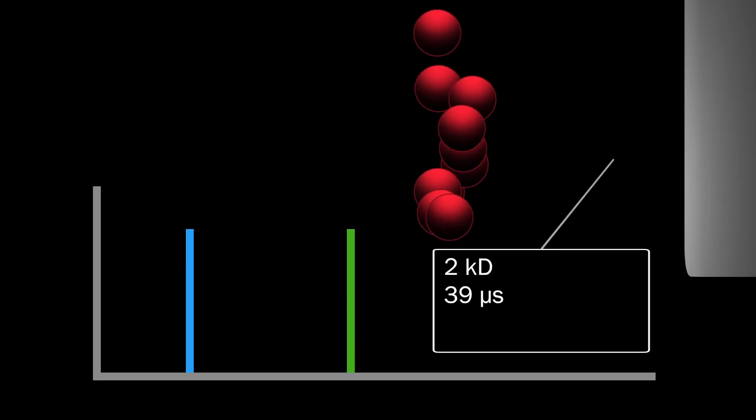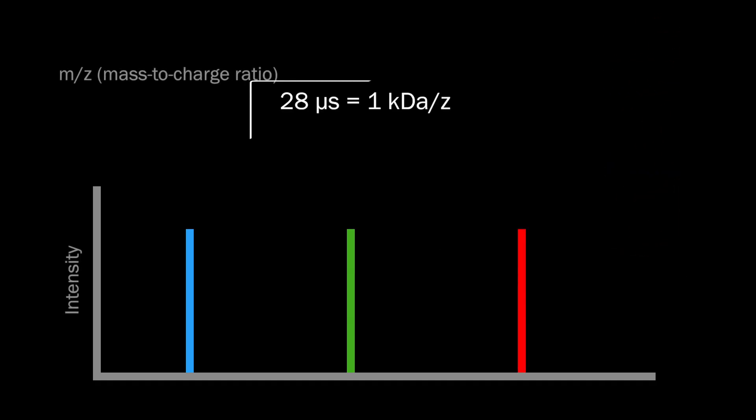The TOF detector then records the time it takes for the groups of ions to travel a certain distance. From our previous examples, for a standard 1.5-meter flight, the smallest ion would reach the detector in around 28 microseconds, the next at around 39 microseconds, and the largest ion in around 56 microseconds. From these times, and the known constant kinetic energy of the electric field, the spectrometer is able to calculate and record the mass-to-charge ratio of each ion it detects.